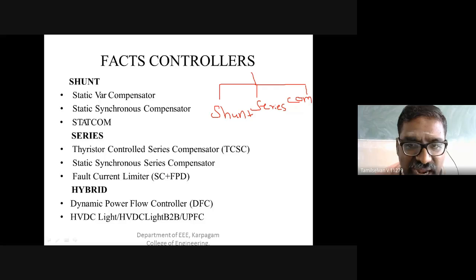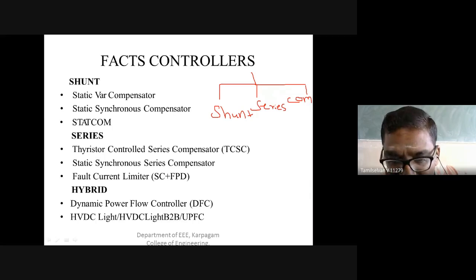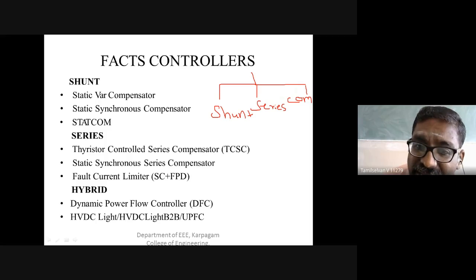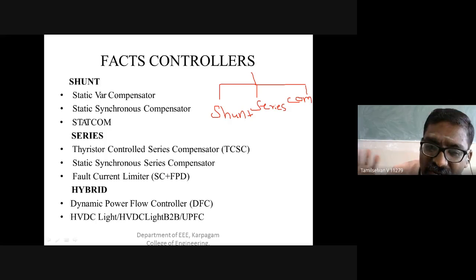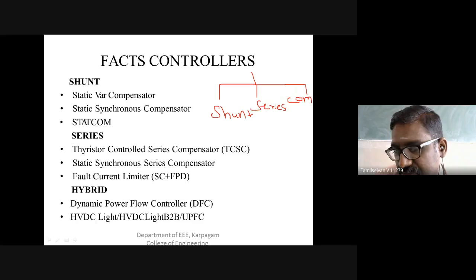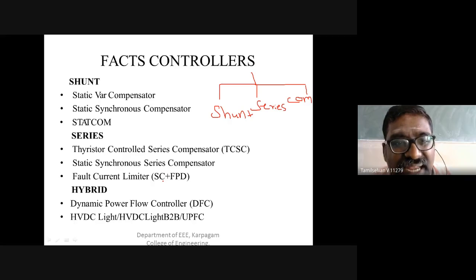This is called a Static VAR Compensator, or SVC. It is a device that can either generate or absorb the reactive power component, depending on whether it uses capacitive or inductive current, so that it can control or maintain a specific parameter in the power system.